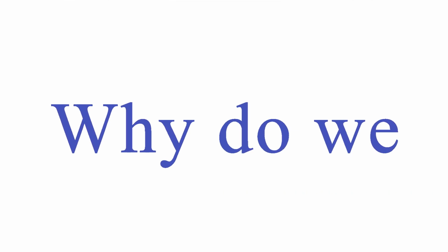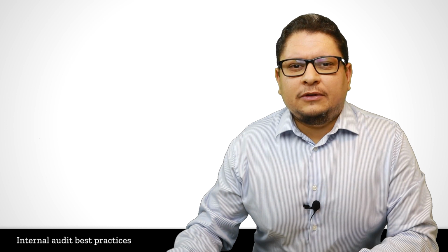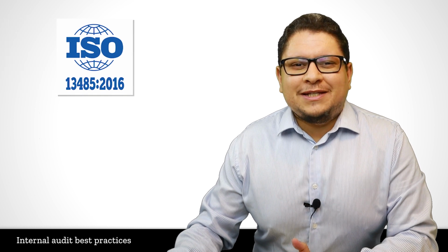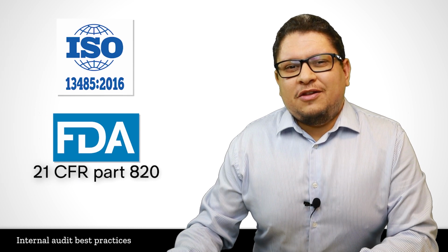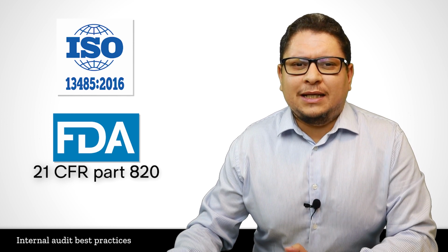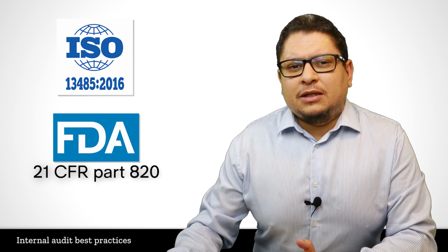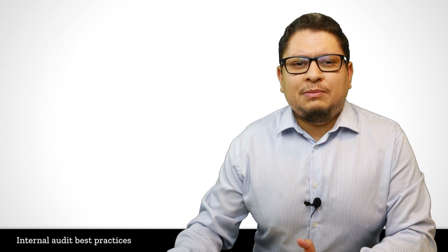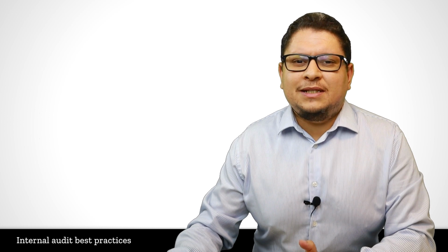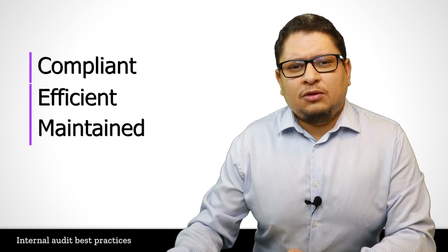So first, why do we need an internal audit? If you are following ISO 13485 or even 21 CFR 820, the internal audit is mentioned there. You need to have an internal audit. Why? Because the internal audit is the tool that helps you verify that your system is compliant, efficient, and maintained.